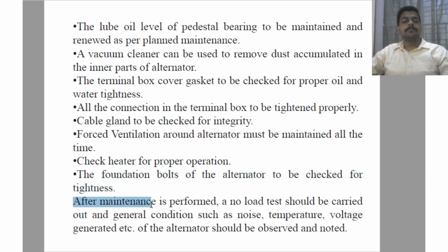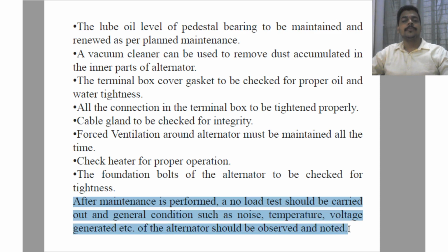After the maintenance is performed, a no load test should be carried out, and general conditions such as noise, temperature, voltage generated, etc. of the alternator should be observed and kept in note.